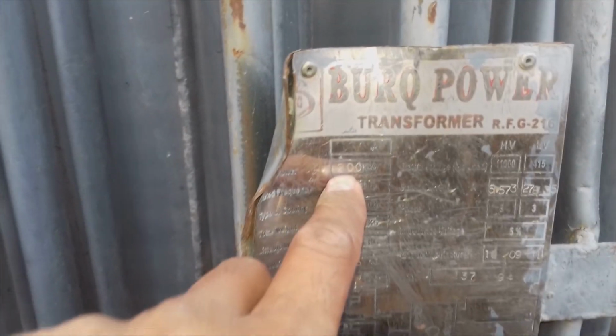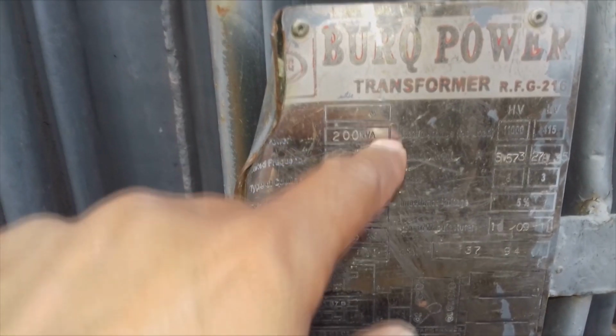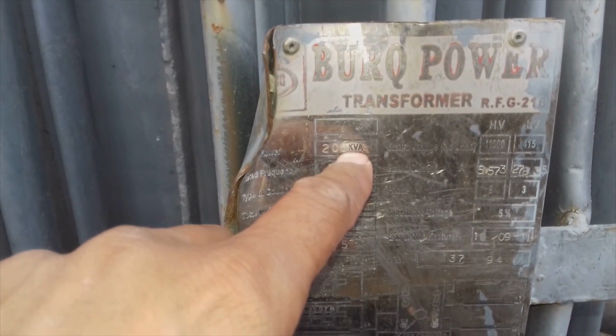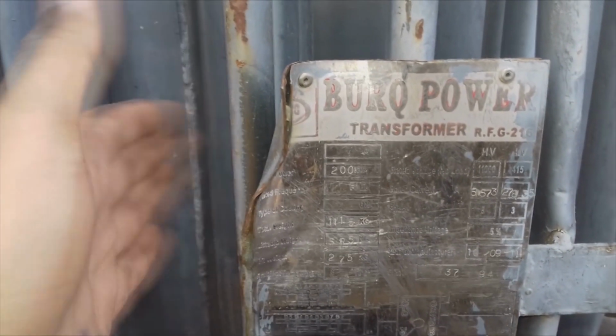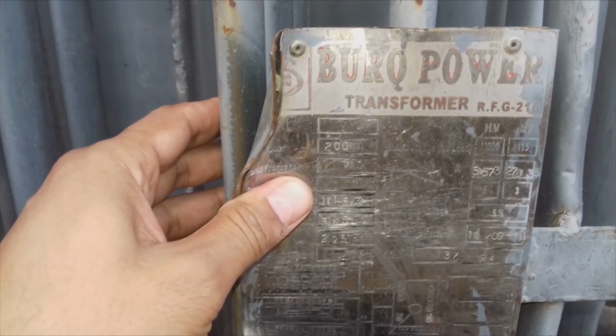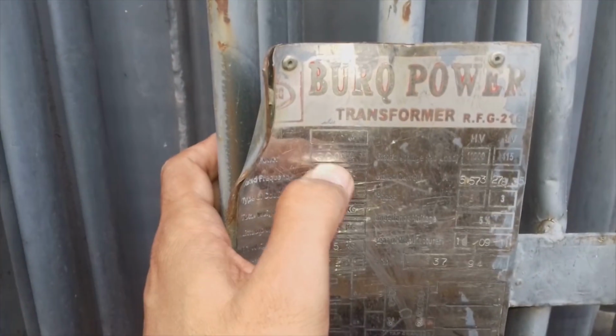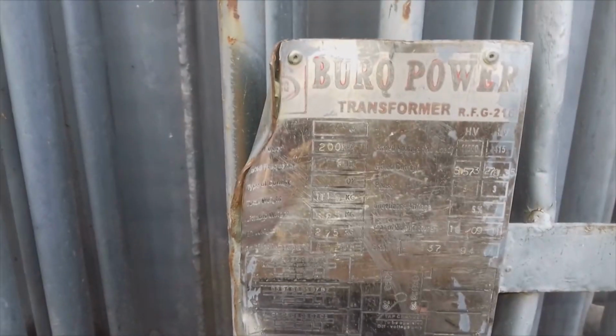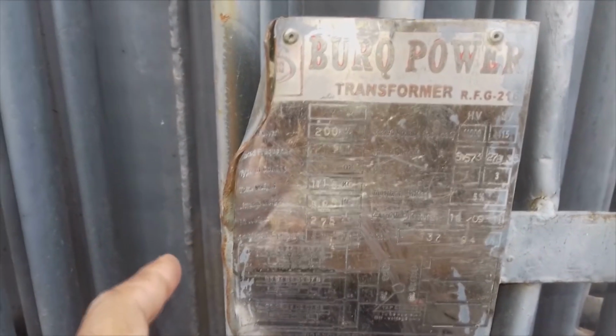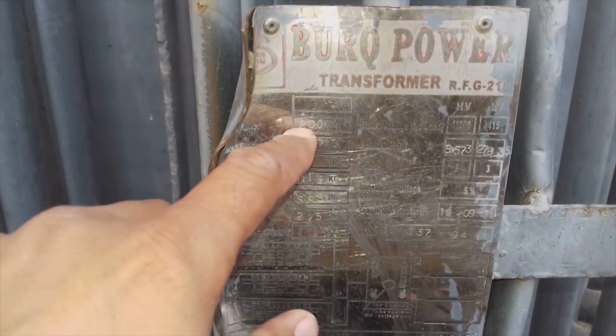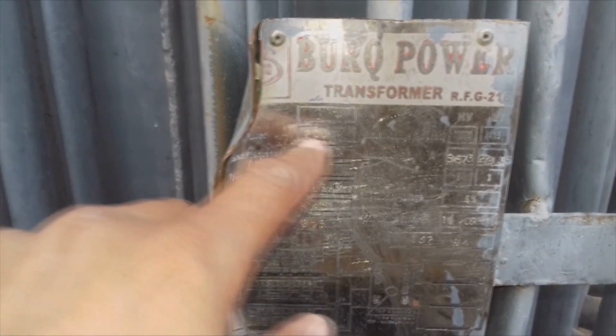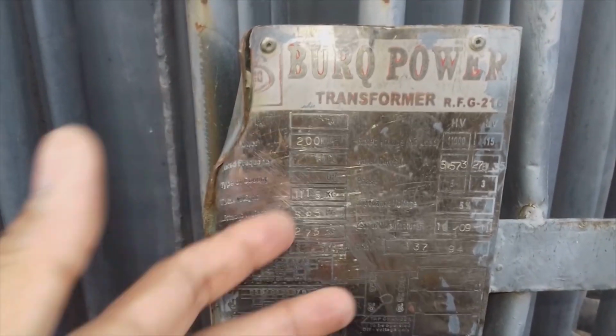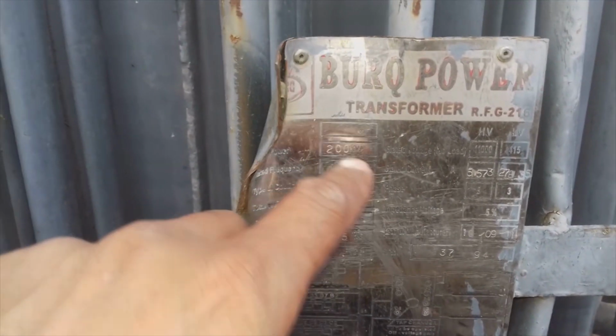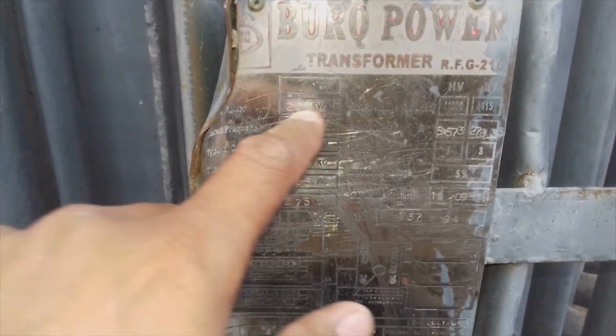So this is 200 kVA. The transformer is normally rated in kVA and not in kilowatt, because the transformer manufacturer doesn't know what type of load you are going to apply on this transformer. So that's why they are giving the kilovolt ampere rating. So here in this case it is 200 kilovolt ampere. They are not mentioning it in kilowatt, because for the kilowatt you need power factor, and power factor is normally for the loads, not for the transformers, not for the sources. Transformer is acting like a source, it's not a load. So that's why it is in kilovolt ampere. So this is normally the question people are asking, why transformer rating is in kVA and why not in kilowatt. So this is the answer.